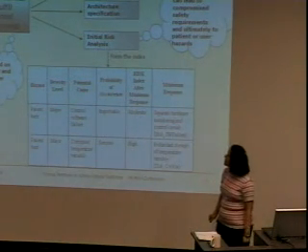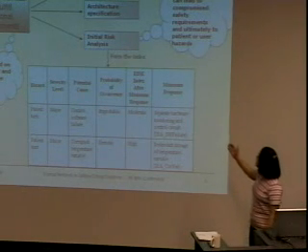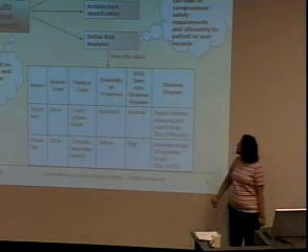There are two hazards defined here. Both of them are patient-borne, but only one of them is due to the software failure. We should say what the probability of that hazard is, and finally, we should define the minimum response if that failure happens.